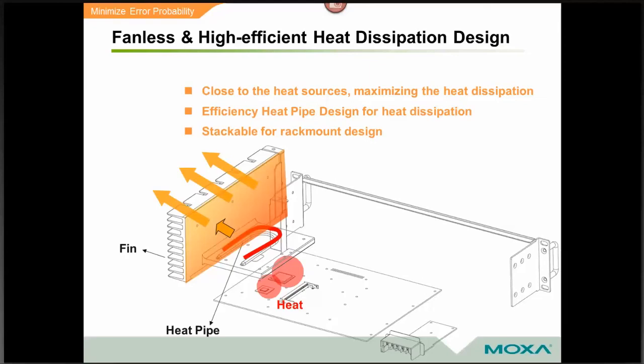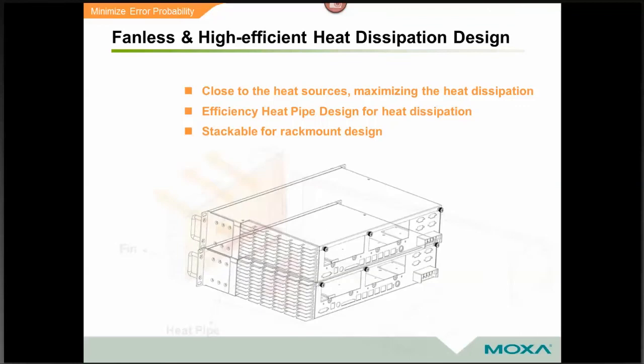In this particular design, we're showing how a heat sink can be placed on the side of the unit so that heat will go up the side of the rack instead of stacking directly on top of another product. So if you had a heat sink in the middle of the product, say, it would just create a hot spot in the middle and then heat up the middle of the next device on top of it, causing an even hotter situation. So you really want to avoid that. This is a good example of how you can do that. There's a couple of vendors that currently participate in this way of dissipating heat. It's a great idea.